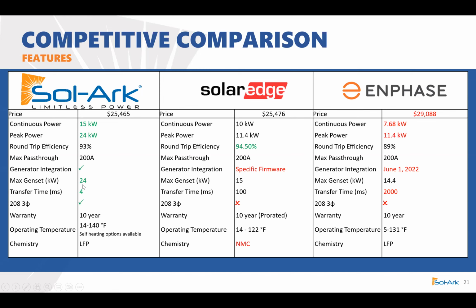We do have a high limit for max genset. On our gen connection, you can actually connect a 24 kilowatt generator with no limitation. And then if you're fully off grid, you can actually connect up to a 48 kilowatt or 200 amps generator off grid. That'll go directly to our grid input. We are capable of 208 three-phase versus our competitors.